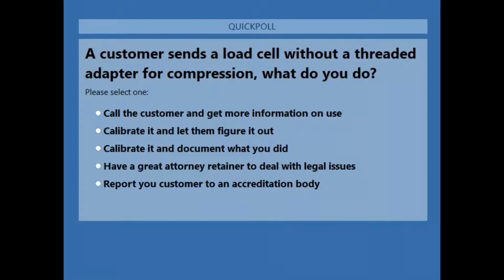If I decide I just want to thread it in an inch, the problem is what's a nominal inch. So I'm going to have some variation with that. But if I say, okay, my compression adapter, I'm going to thread it in an inch. It's got a spherical surface, and then tension adapter, I'm going to thread it in an inch and lock it down. You can mitigate that error. Tension, more so, it pulls away, but you can mitigate it. The best thing is just to lock it into place, or if you really need to, the button cell is going to give you that, because there's all that meat in the center.